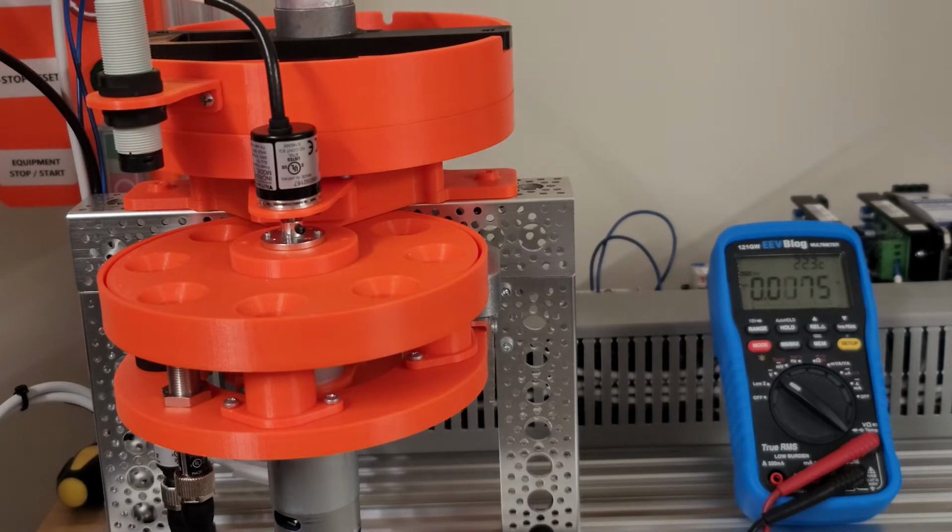The thing I want to do first is verify that our output matches what we expect it to be. So, given the specific motor's relative RPM and our scaling, I've set the program to just throw an output into the scaling logic that is exactly half of the RPM.